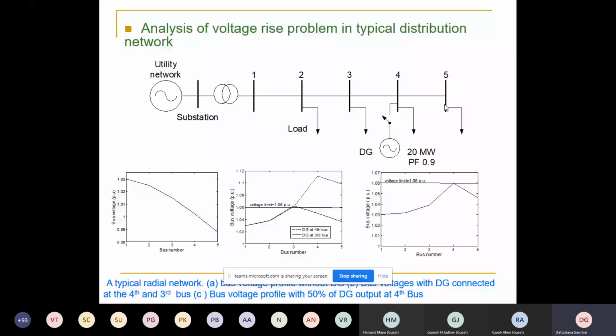Now try connecting one DG of 20 megawatts—imagine it's wind or solar, whatever the DG may be. We're talking about steady state analysis here. Imagine that connection and run your load flow. You'll see the voltage goes up to a very high value, above the limit—here, and here, above the limit at the 4th bus, which is where you connected it. It violates the limit. So what the operator does is shut down the supply because voltage is going up and he's not able to keep it constant. Otherwise, he has to pay compensation because load may get damaged.